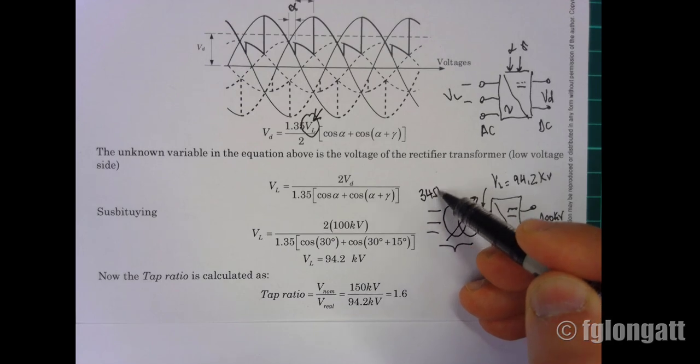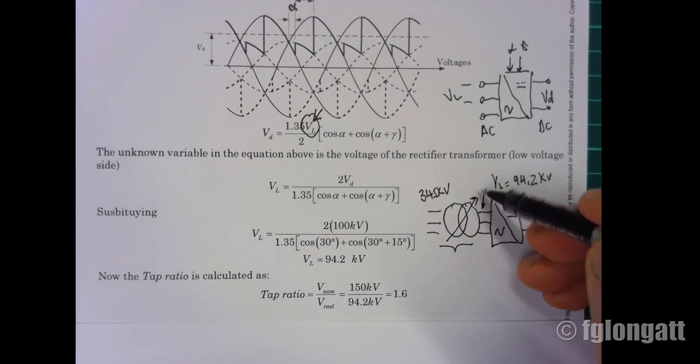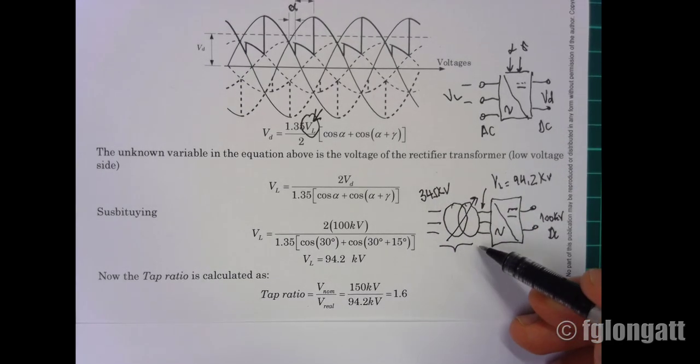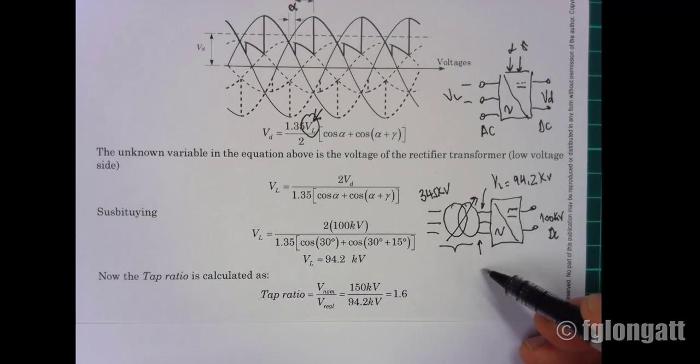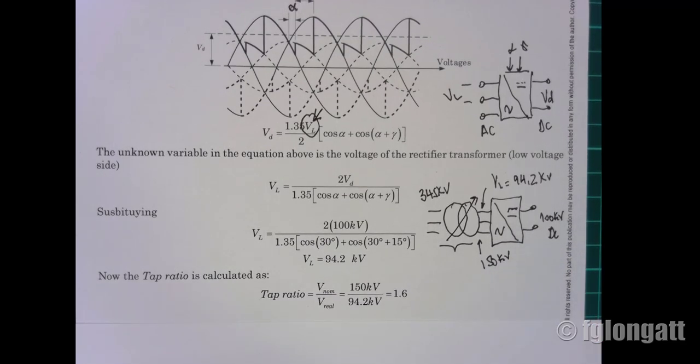Now, if the tap changer is located at position neutral—the central point—the voltage should be 150. But because we are using a lower voltage, 94.2, we calculate the ratio, the tap ratio.